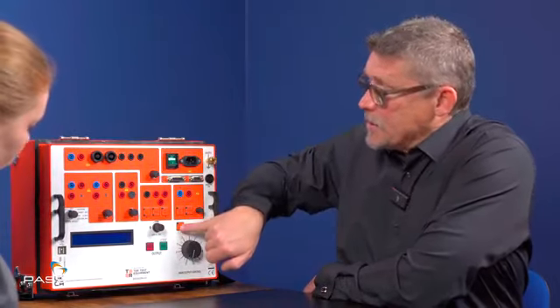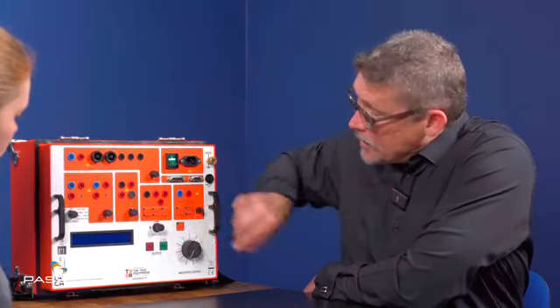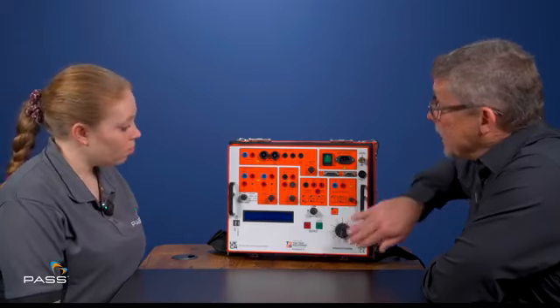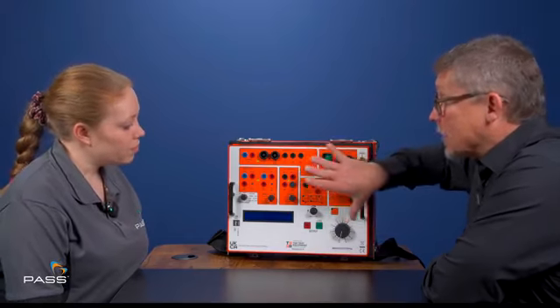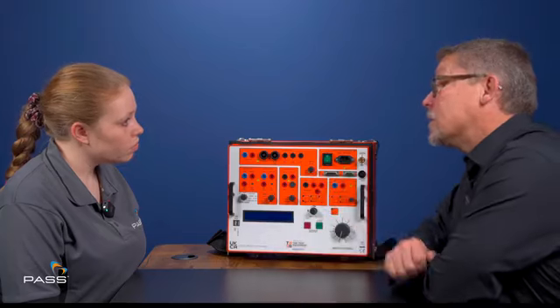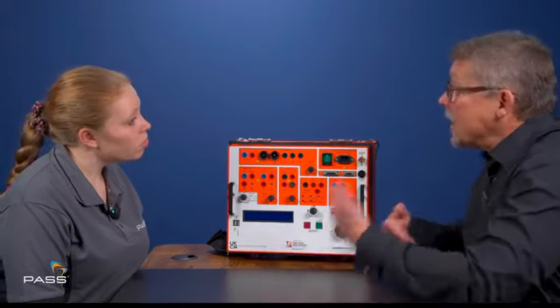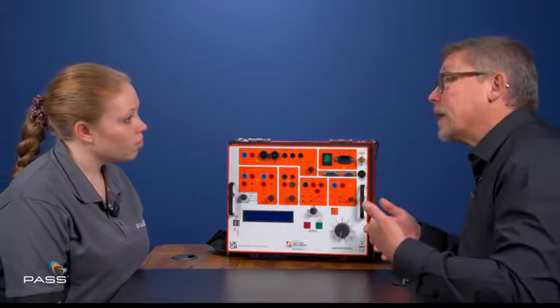So we've got the resolution here, but here we apparently don't seem to have very good resolution, except for the fact that I have this I limit button. So when I turn this, if one was 1 amp, for example, if I hit the I limit, that one would be 0.1 of an amp. So I then get extra resolution here and extra controllability to test those digital relays. So that is in addition to testing the older mechanical relays.